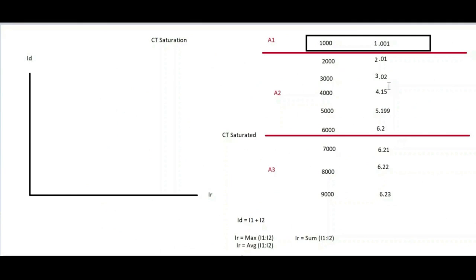Okay. So now let us see what happens from 0 till 1000 amps, that is still the full load current. The current is having a specific type of error, and this error is fixed. It will not change. This is defined by your CT manufacturer. So let us say the CT nameplate detail says that this CT has an error of 0.01%. That means up to full load current, your error will be constant.